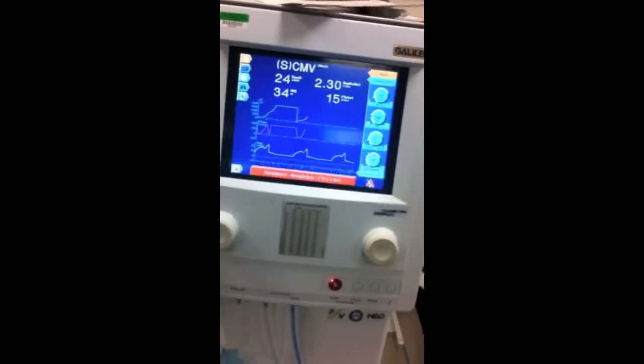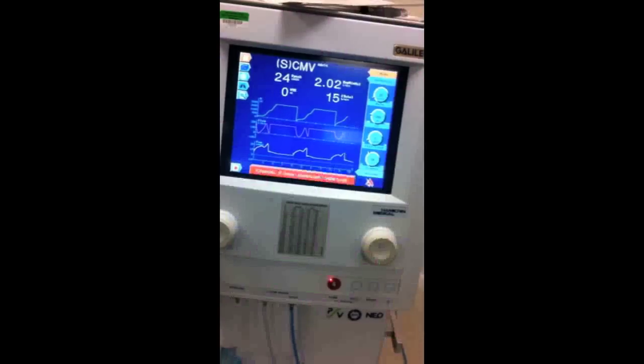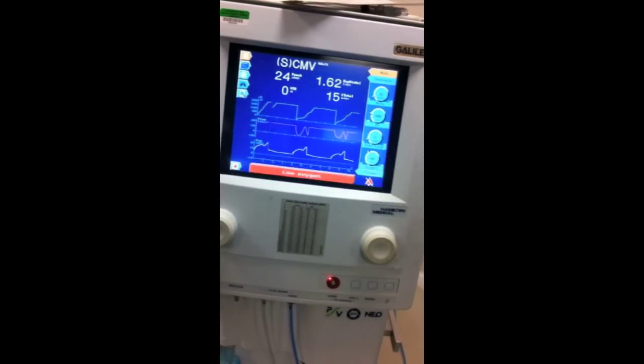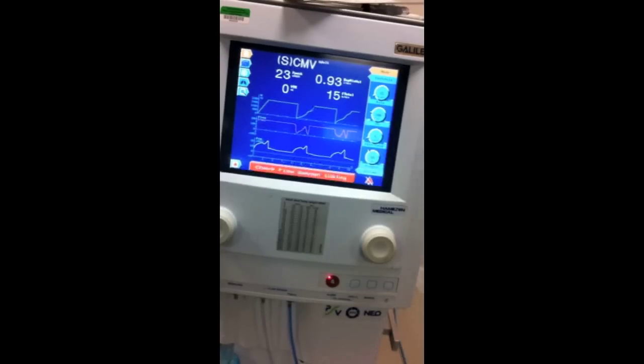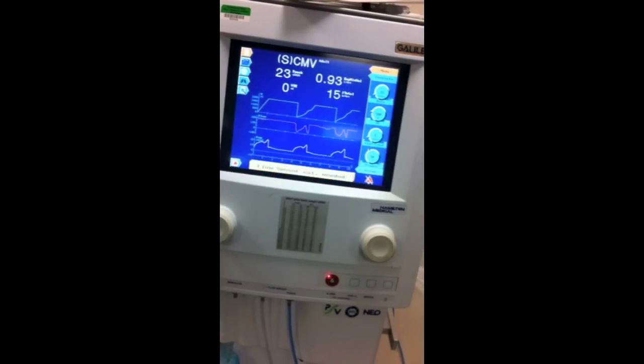I can't do that at that angle with that hand. And so that'll go away. And then you'll do the same thing with the air. And then you check the high pressure. So it'll have you kink the tubing so you confirm that the high pressure alarm goes off. Things like that.